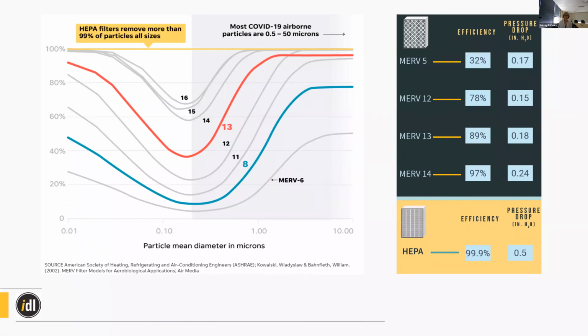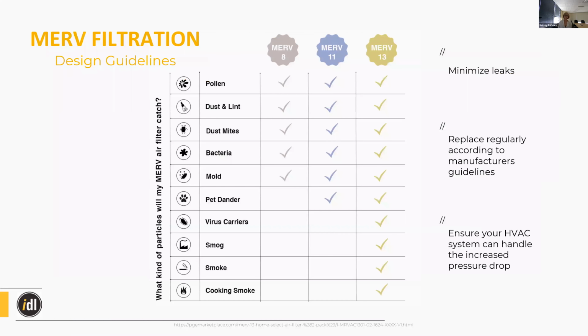So if your HVAC system can accommodate it, meaning your fans can push that air through there without being damaged and having to be replaced, then upgrading your MERV filter is a really simple, easy way to go. Virtually the maintenance is the same. You're probably going to change it every 6 months or so according to the manufacturer guidelines. But yeah, maintenance is really easy. It's just that operating cost that sneaks up on you just a little bit on this one.